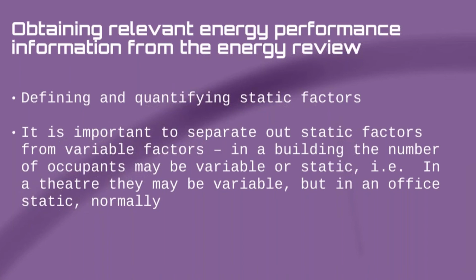So the floor area that would normally be static in that sort of situation is going to change day by day depending on who's booked exhibition space. But you still need to check whether that was significant or not. It might be that even though only half the exhibition hall is in use, the rest of it is still being heated, and maybe if it's not being controlled very well, still lit, and it's actually not, whether it's full or half full, it's not affecting the energy use.